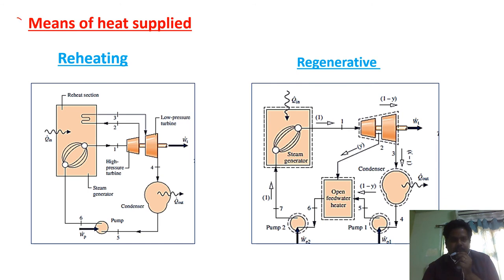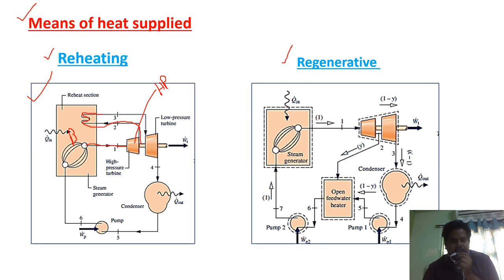The next type of classification is by means of heat supplied. There are mainly two types: reheating and regenerating. In reheating, as you can see in the schematic of the reheating cycle, water in the boiler is converted into steam. That steam enters the high-pressure turbine. After passing through the high-pressure turbine, instead of going to the condenser, it goes to the reheat section where steam is reheated, and then sent to the low-pressure turbine.